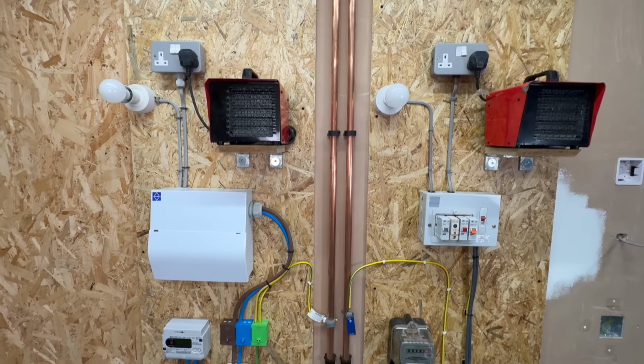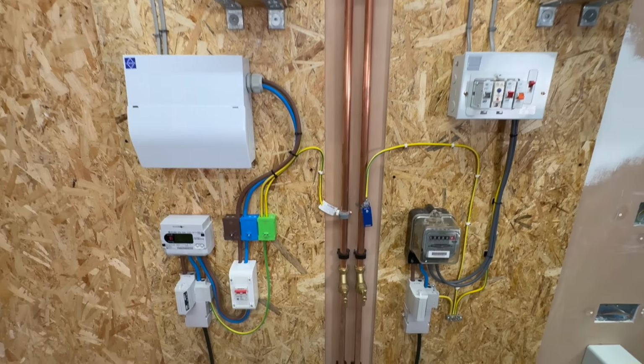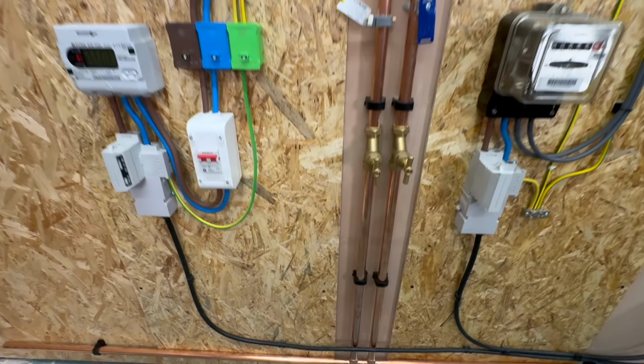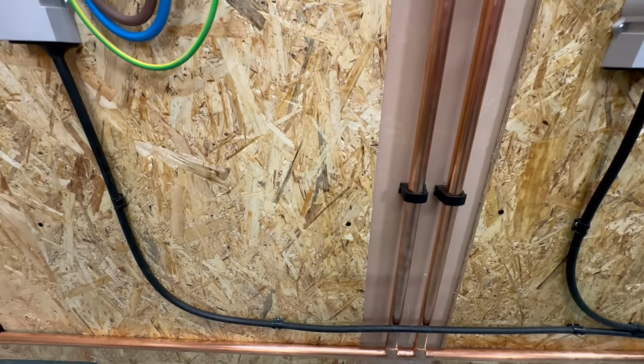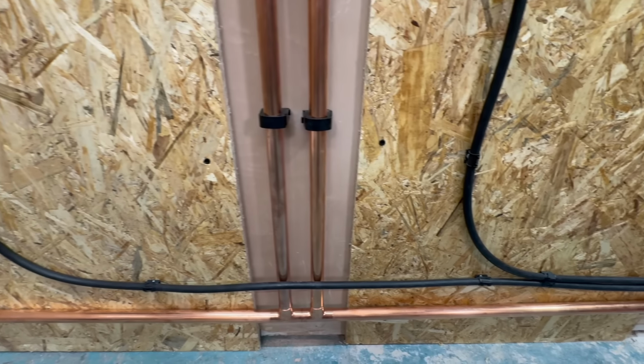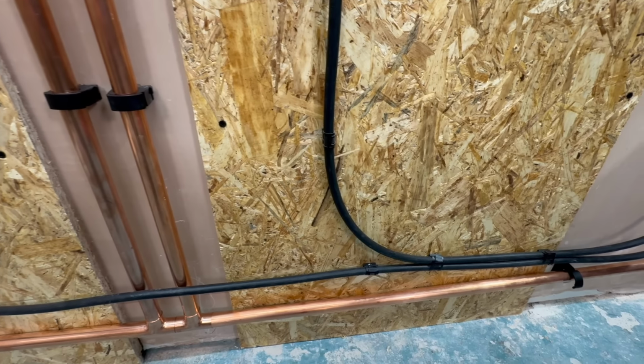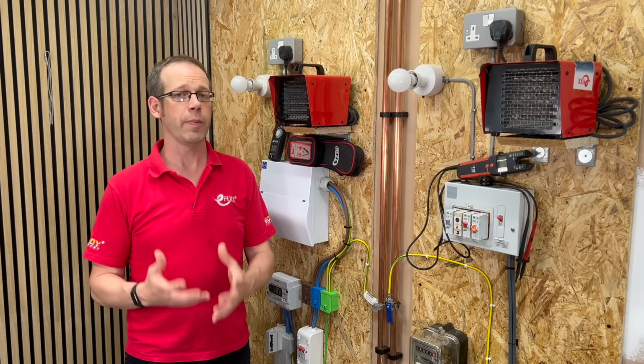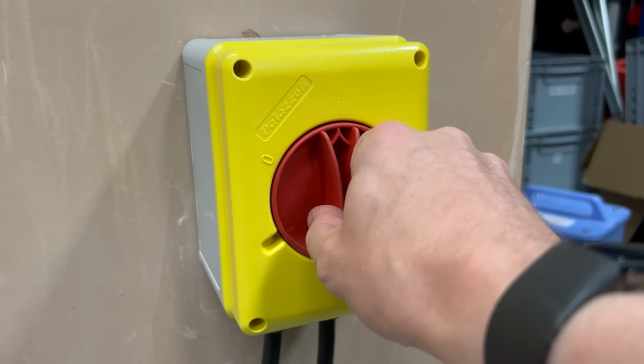In the first, we've got 2 properties side by side, both with an incoming water supply in metal tubes connected to a metal pipe between the properties. If the old creaky combined neutral and earth connection to the main supply cable has become disconnected, then a major problem becomes apparent. Or does it? I'm going to simulate this happening on my demo rig here.